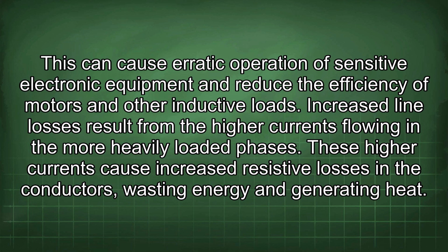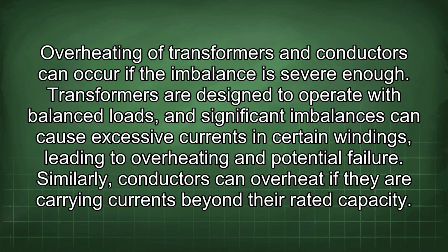Increased line losses result from the higher currents flowing in the more heavily loaded phases. These higher currents cause increased resistive losses in the conductors, wasting energy and generating heat. Overheating of transformers and conductors can occur if the imbalance is severe enough. Transformers are designed to operate with balanced loads, and significant imbalances can cause excessive currents in certain windings, leading to overheating and potential failure. Similarly, conductors can overheat if they are carrying currents beyond their rated capacity.